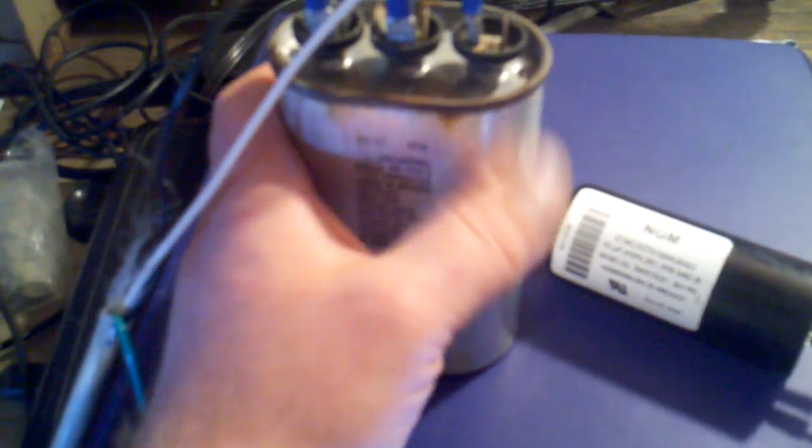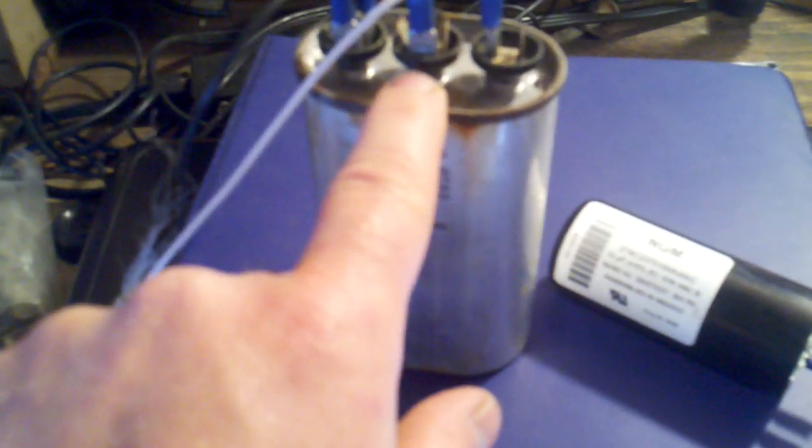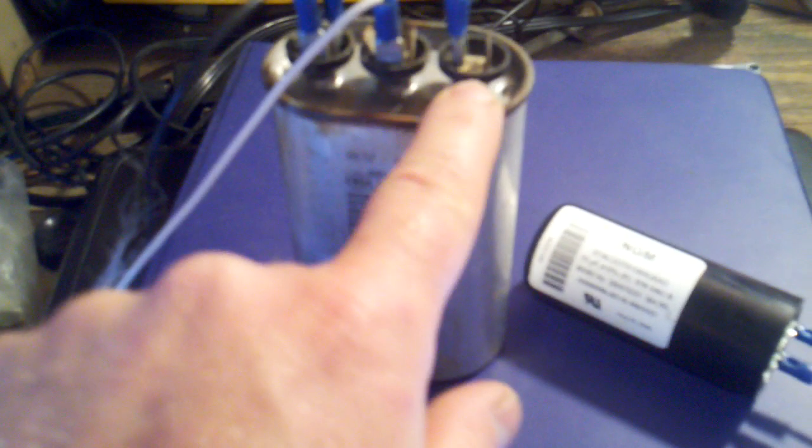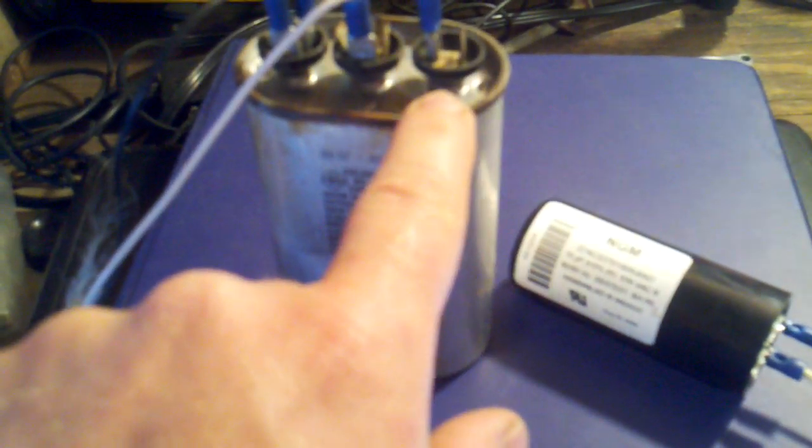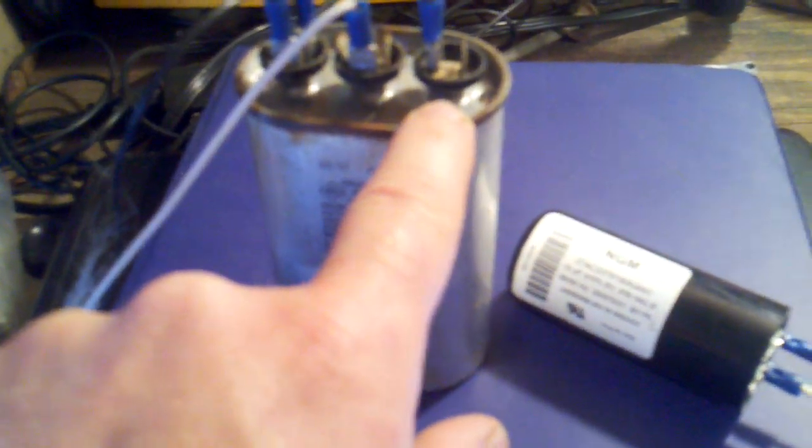Common to fan would be the 5 microfarad running a little fan. Common to herm would be the 35 microfarad. So I have common and then running in parallel is 5 to the 35, so I have this hooked up as a 40 microfarad capacitor.